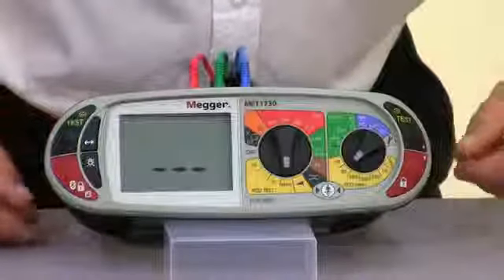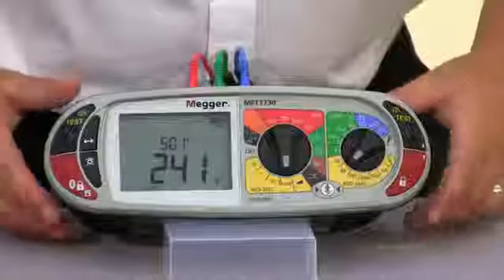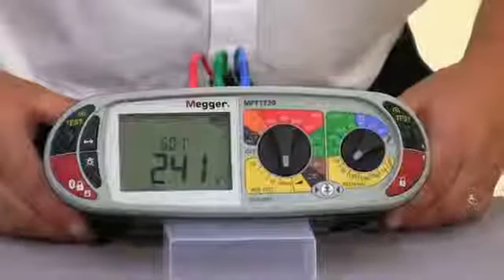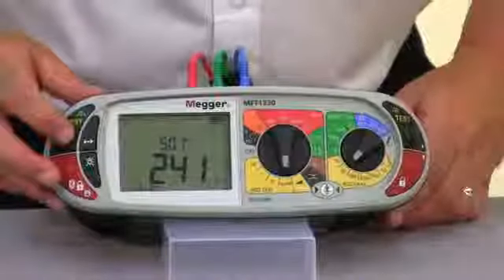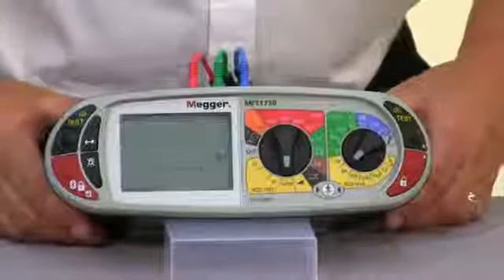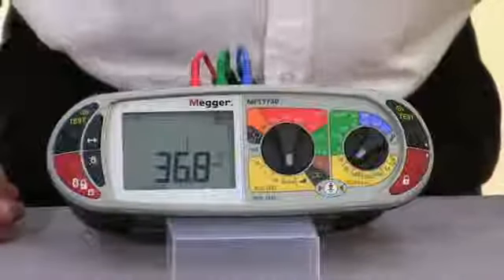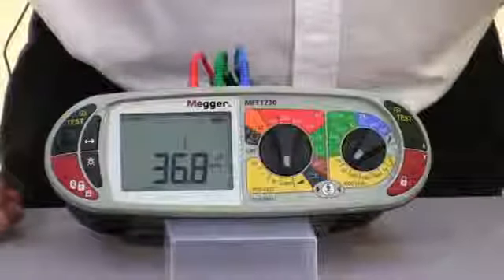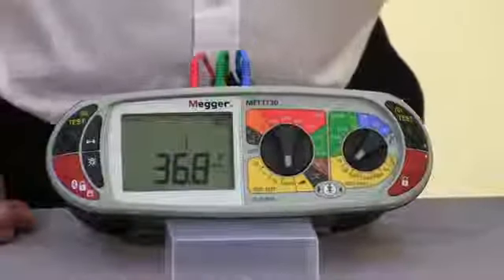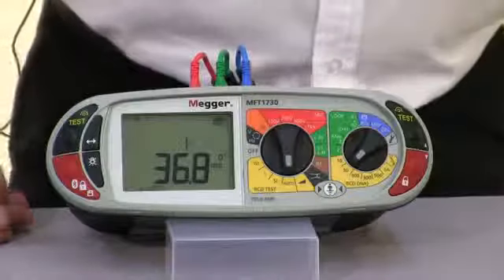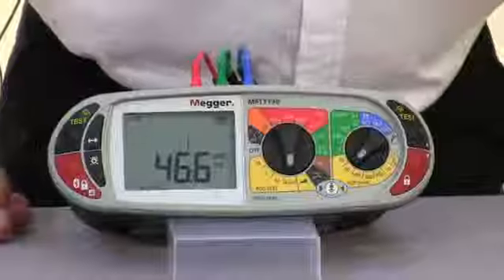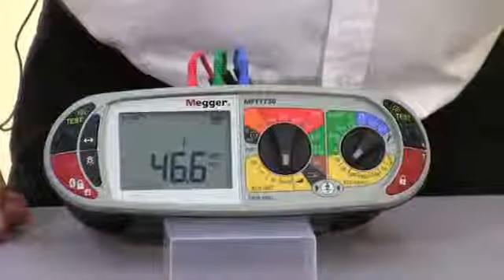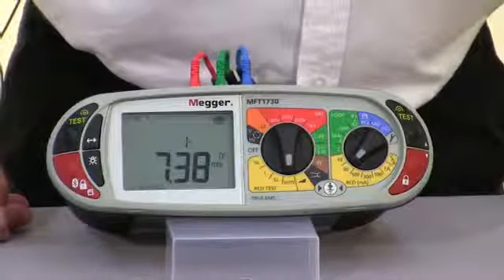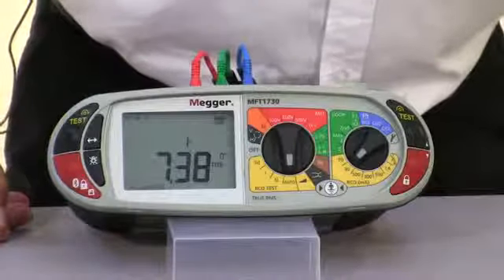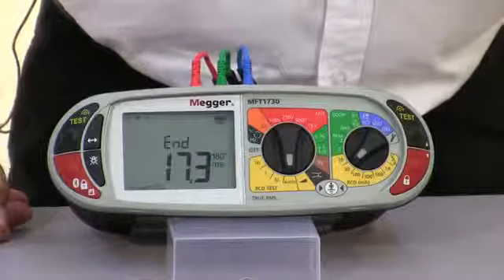So what I'm going to do is select the auto test for a 30 milliamp RCD. Now you can set the MFT to auto start, but I've got this defaulting to a manual start. So initiate the test sequence and it will then run through all the required tests. In the first instance we're making sure that the unit doesn't operate with a times half test. It's then gone straight in and done a times 1 test at 0. So resetting the RCD, it will repeat the times 1 test at 180 degrees, reset again, and it ups to 5 times the rated current at 0, and finally 5 times at 180.